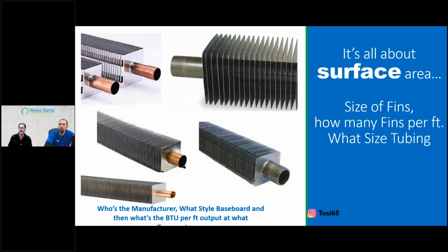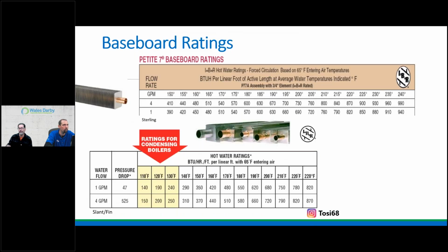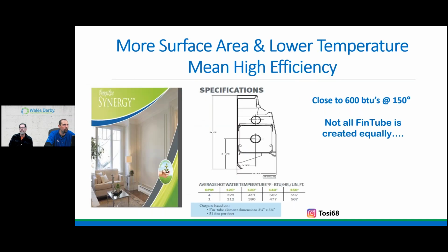It's all about surface area, right? Bigger here, oversizing more of it than required allows us now to lower water temperature. All right, here's again charts showing you it's not only 180, right? It's less water temperature, less BTU output, but I have more surface area, so therefore I equalize what the envelope requirements are. Again, manufacturers have even gone to the extreme.